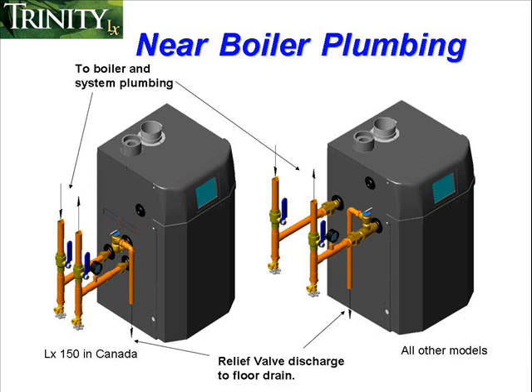All Trinity Lx models also come factory supplied with a pressure gauge. Models that are dual certified as either boiler or water heater also have an additional factory supplied pressure gauge at a higher PSI rating. For boiler installations, either the lower or higher pressure gauge may be used. The pressure gauge must be installed at the appliance's outlet prior to any circulators and in the general vicinity of the pressure relief valve.